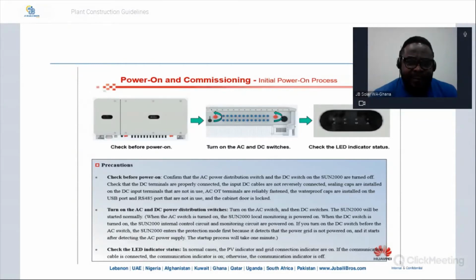To power on this inverter, it's a simple system. It depends on whether you are doing a residential system or a C&I. Since the residential is the longest, I will use that as an example. So imagine you are going to power on a residential inverter that has batteries in the system. If there are batteries in the system, first rule, switch on the batteries. So you switch on the knob on the battery first. Please take note, battery first, then AC switch next, before DC switch. So it goes in that order. Battery switch first, AC switch next, DC switch third.